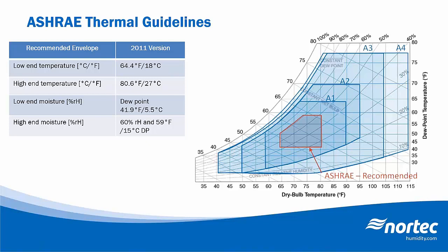So looking at the recommended envelope, the recommended temperature range is now 64.4 degrees Fahrenheit to about 80.6 degrees Fahrenheit, with a moisture range of 41.9 degree dew point to about 60% RH at a 59 degree dew point. And really that minimum recommended moisture limit is provided to protect equipment from ESD-induced failures. And the high limit is there to provide a reduced risk of condensation on the IT equipment itself.